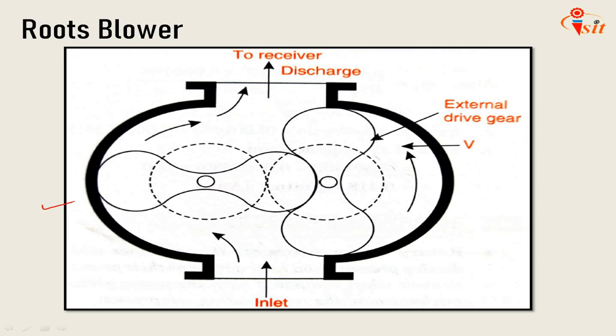This sealing continues until delivery commences. There must be some clearance between the lobes, and between the casing and the lobes, to reduce wear. This clearance forms a leakage path which has an increasingly adverse effect on efficiency as the pressure ratio increases.